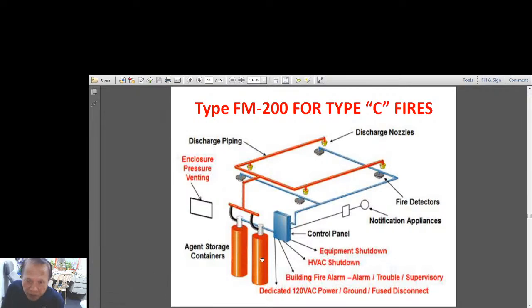You will notice that there are fire detectors. This one, this one, this one, and this one. And they would send a signal to your control panel which would automatically allow the flow of the discharge of the agent. Okay. Enclosure pressure venting. There's also the equipment shutdown, HVAC shutdown, building fire alarm, and dedicated controls. Okay, so that's how this FM200 operates. Similar to Inergen also and Novec. Almost similar.